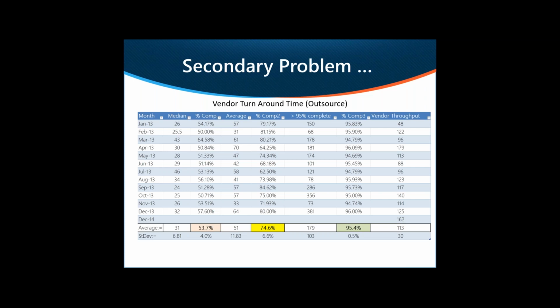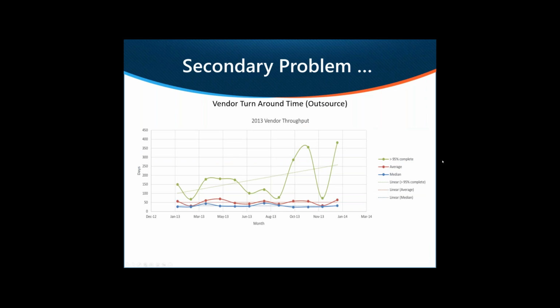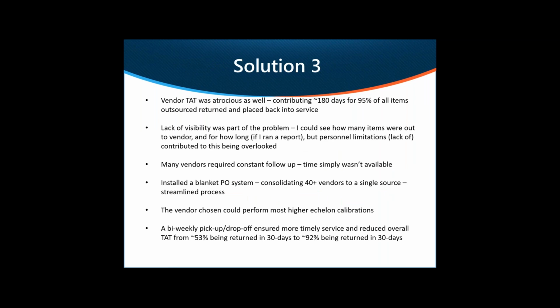Secondary problem, vendor turnaround. Although the vendors suffered a lot of the same thing as the internal turnaround time, which is that people weren't coming to pick it up, there was also a secondary issue with that as well. If you look at it, the median time was about 30 days. The average is about 50 days. I typically see 30 to 45 days for most vendors from dock to dock. But again, 95% of all the equipment that was turned back to the customer that was vendor related looks very similar to what was going on with the internal calibrations. And sure enough, that was part of it.